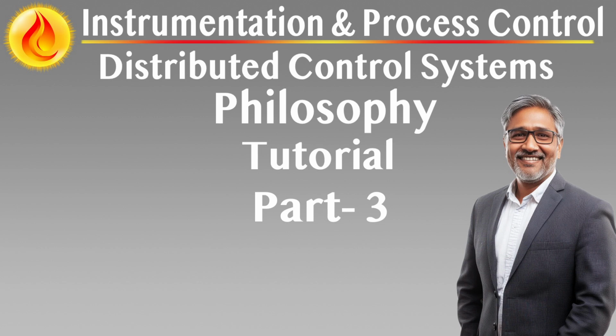Operator interface and visualization. Unified operator display. FGS status, detection points, overrides, and fault diagnostics are presented on DCS and dedicated mimic panels. Graphical overlays show fire zones, detector types, active alerts, and suppression actions in real time. Zone-wise mimic panels. Physical LED-based mimic panels present clear visual status of detection zones and system state. LEDs are color-coded by hazard type, e.g. gas, fire, fault, and grouped by plant area for rapid situational awareness.